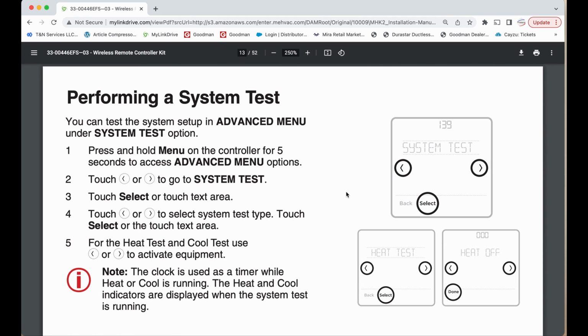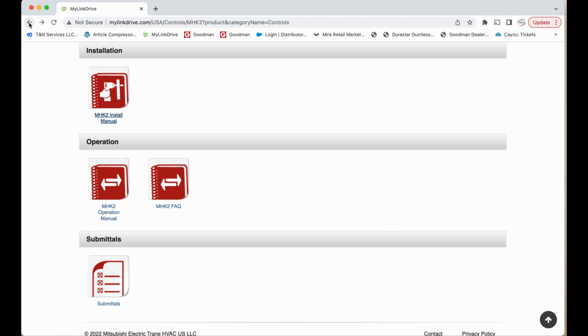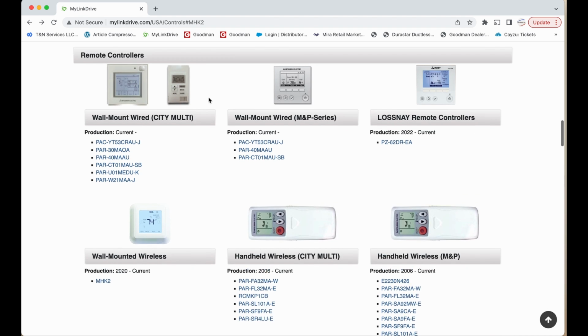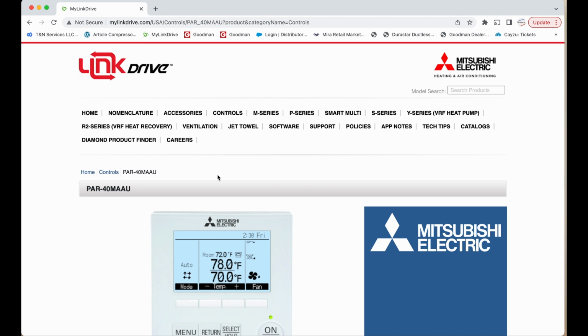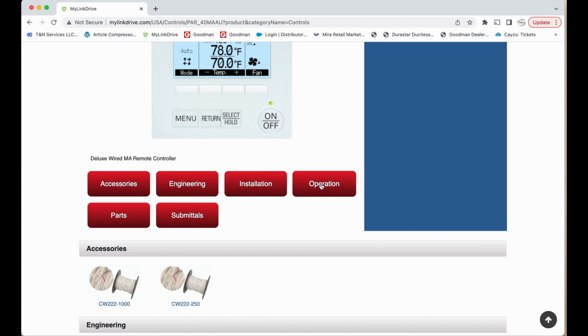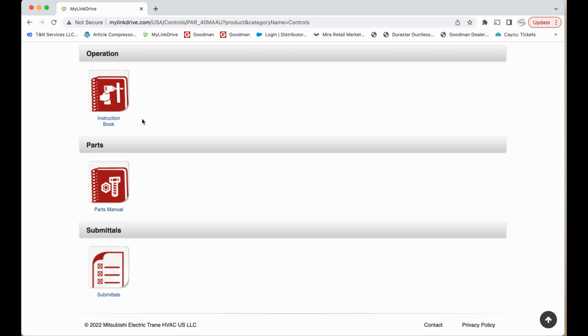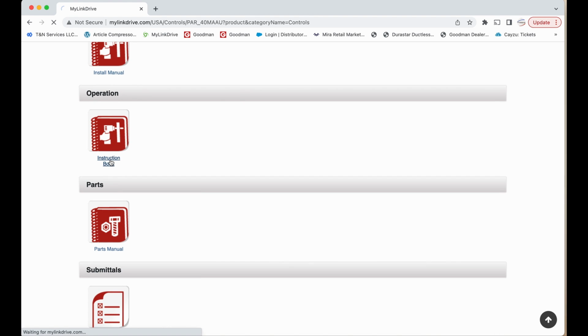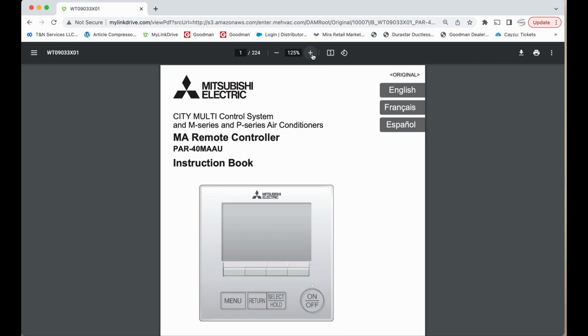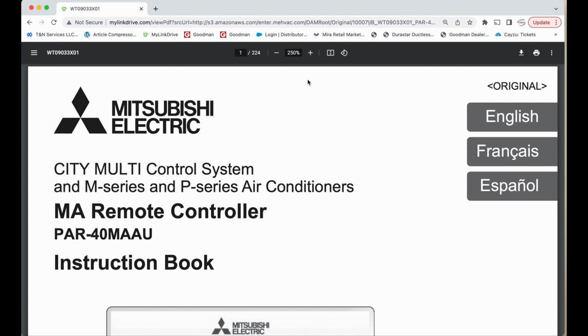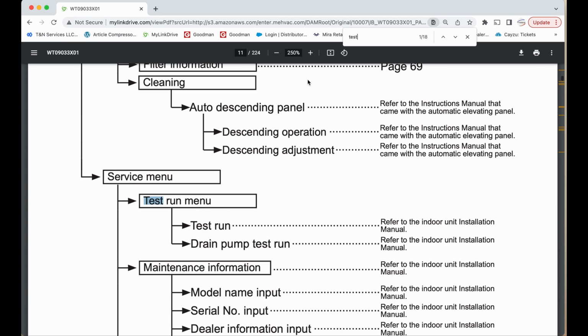Now, what if you have a wired controller? What do you do at that point? So we're going to get back out of here. We're going to go up to a PAR 40 controller, and we go into the operations menu. This one right here, the instruction book. You can scroll through this if you want, but I'm going to do the Command F or Control F and hit test. And it takes you right there. So test run menu. It tells you that you have to go into the service menu and then test run. Okay, and that's how you get into the test run on a wired controller.